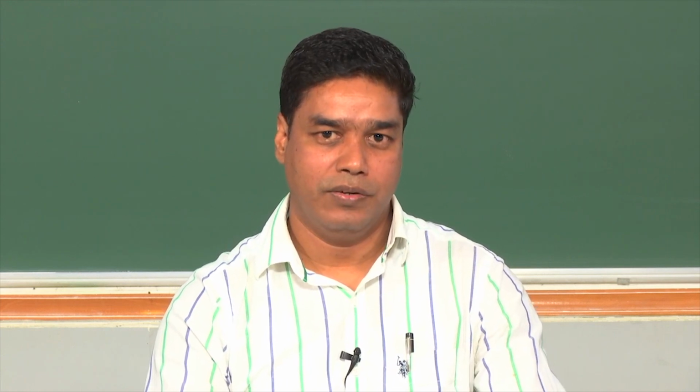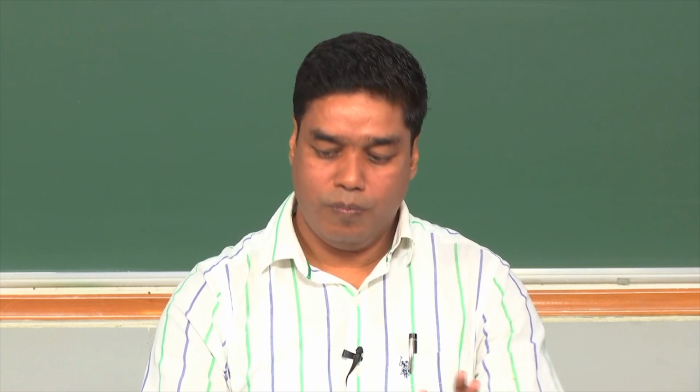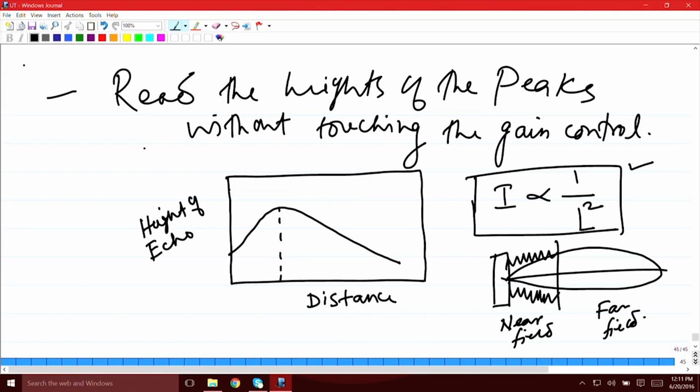Okay. The signal intensity which is being received by the probe within the near field will increase as the distance is increased within the near field.